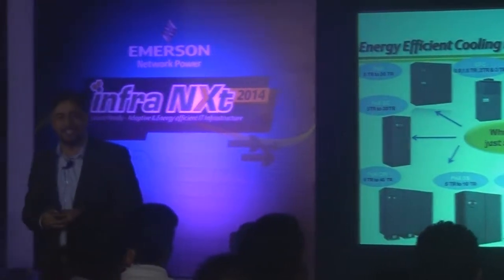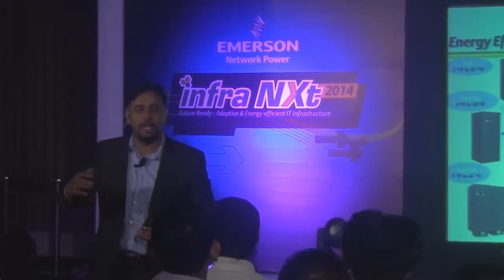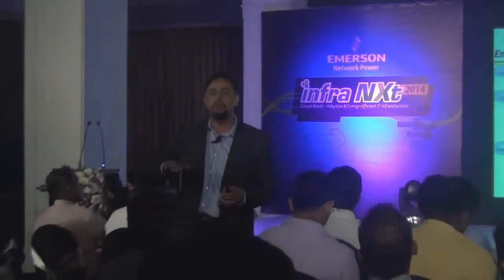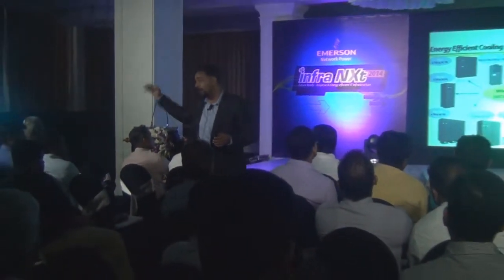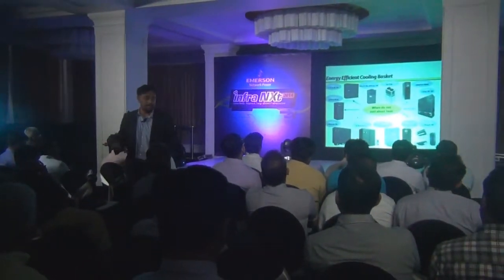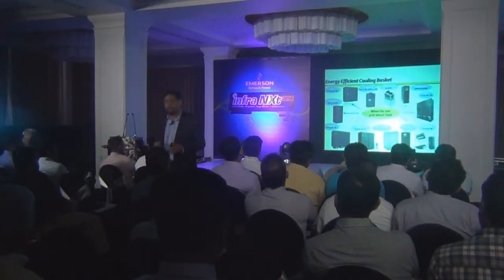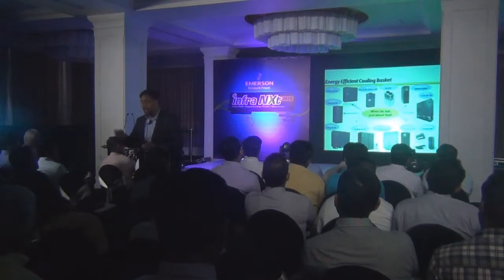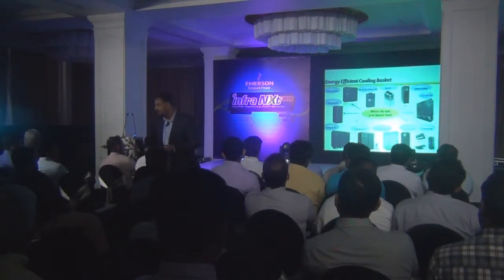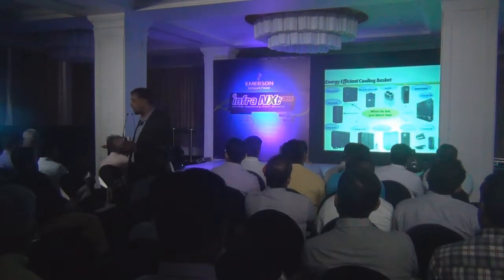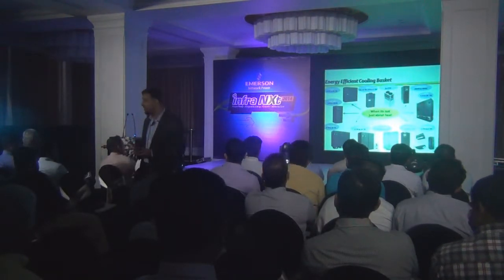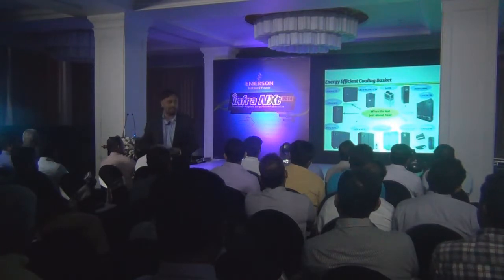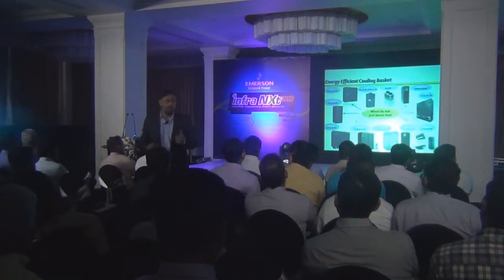When you say variable loading pattern, why do you need variable capacity in the data center? Because when you size any kind of cooling system, we size it for the maximum ultimate load which is supposed to come down the line for the ultimate design capacity of the data center or server room. But that is not a load available on day one, and your ambient is never fixed. It's different at night, day and across the year. And then your internal load on the servers or switches also changes. So that means your overall load in the server room or switch room is never fixed. So why should the air conditioning be with fixed capacity? And why do we have to pay for fixed capacity? Even if the load is less, it works more and you pay more.